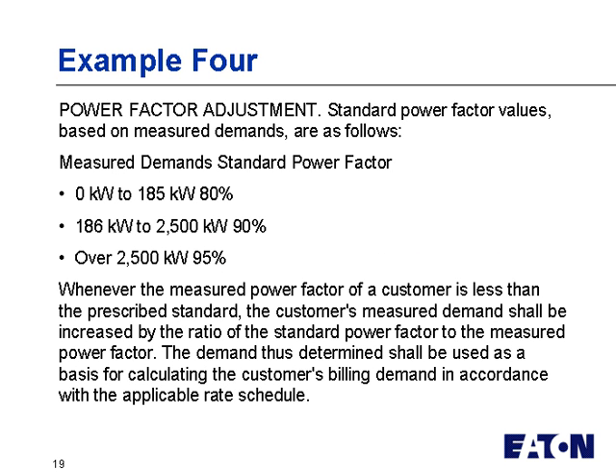The next one is just an example to show you that for various load sizes, for example, 0 to 185 kW, you're required to maintain an 80%, and over 2,500 kW, you're required to have a 95% power factor. So obviously for larger customers, they don't want them to have lower power factor, or they're going to incentivize them to actually correct the problem. And this one, again, adjusts the demand based on what your actual power factor and your load is.